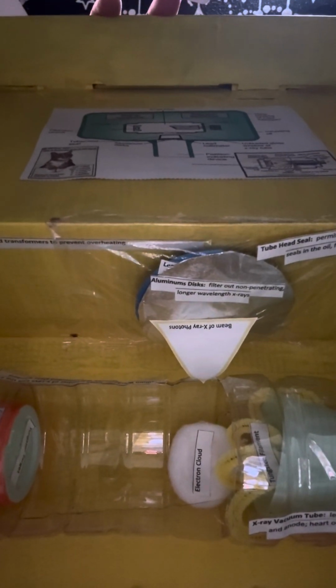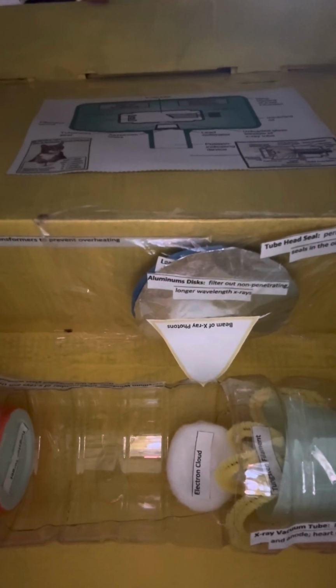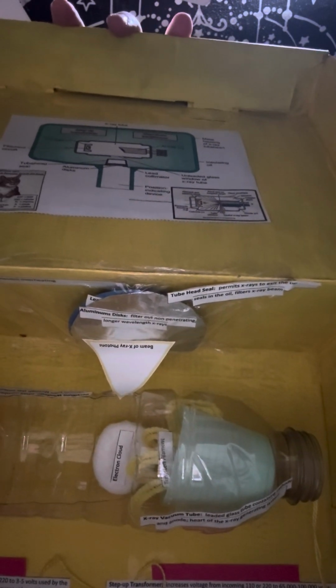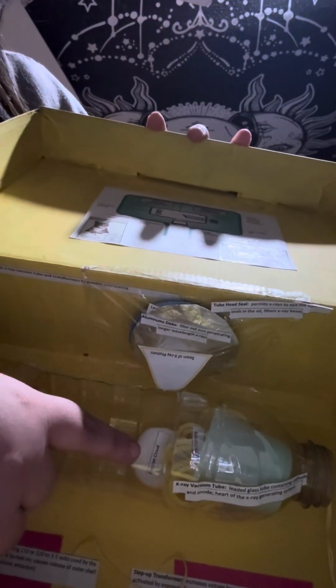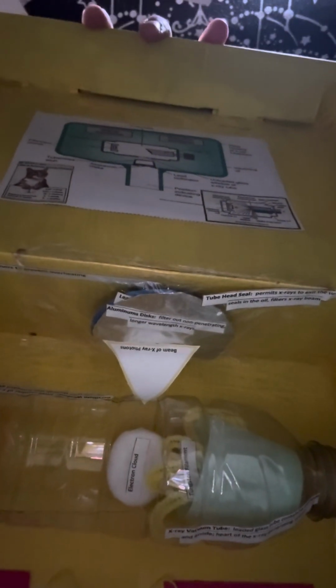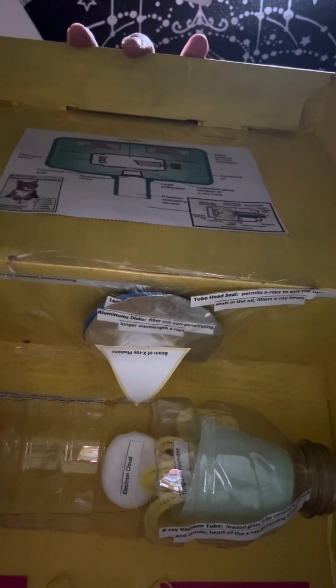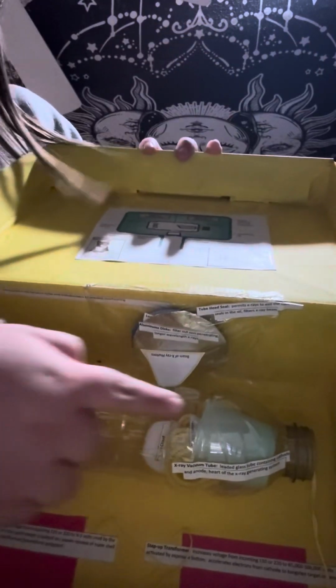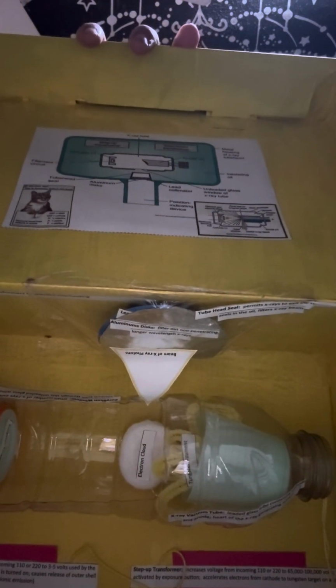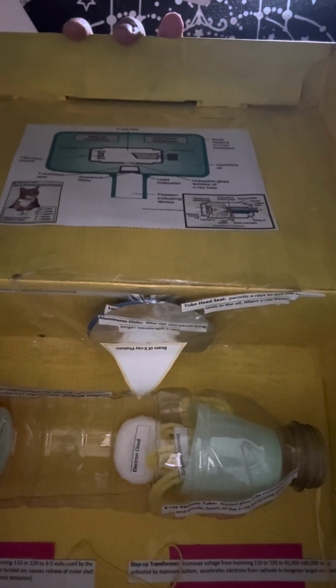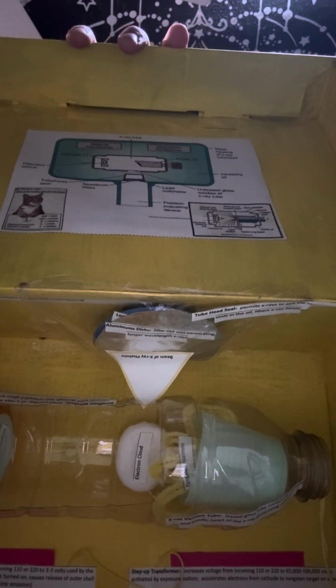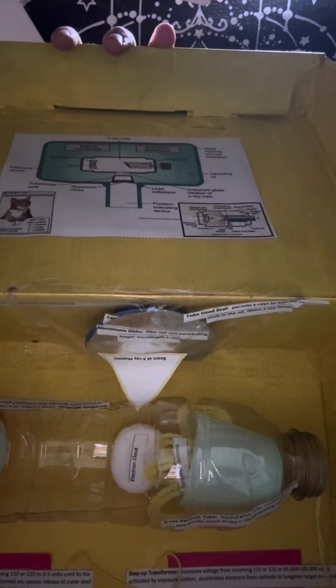And then after that, we have the cathode. It helps supply the electrons needed to generate the x-rays, and they are negative electrons. And we have the tungsten filament, which is over here on the side, and that helps produce the electrons when needed. When heated up, it can help produce the electron cloud. And then we have our molybdenum cup, which focuses the electrons into a narrow beam towards the tungsten target. This is our cup right here. And then we have our anode, which converts the electrons into x-ray photons, and it is positive. And the tungsten target serves as the focal spot to convert the electrons into x-ray photons. And lastly, we have our copper stem, which dissipates the heat away from the tungsten target. And over here is the copper stem.